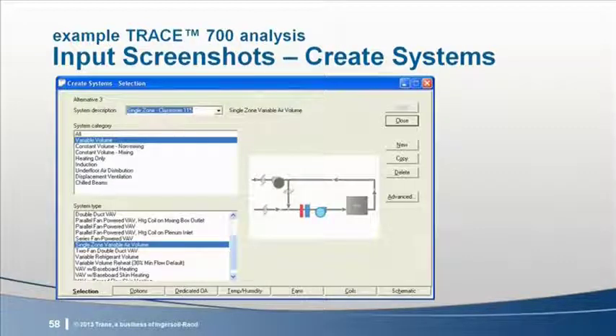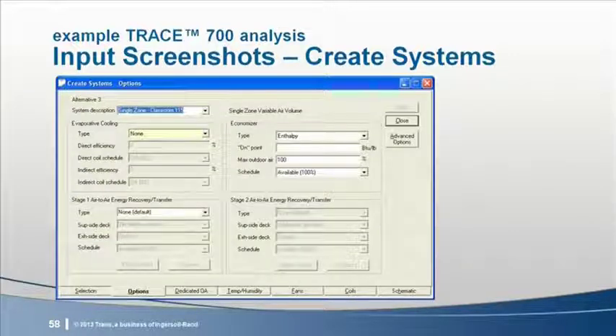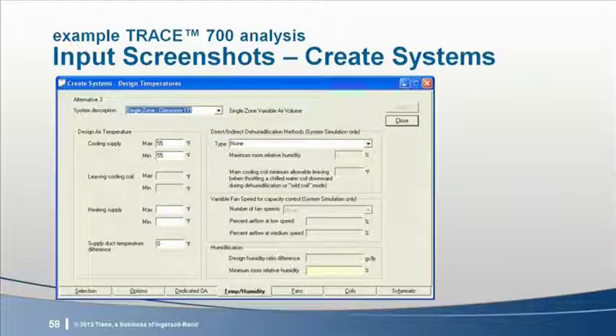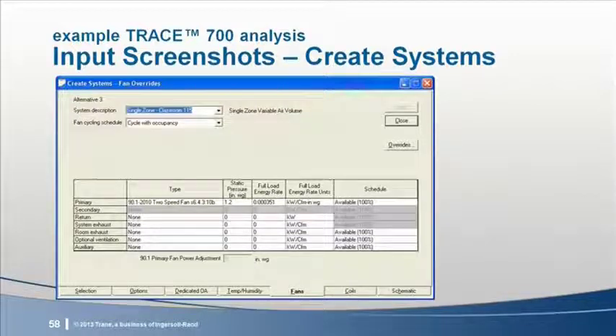Simulating SingleZone VAV systems within Trace is quite simple. First, select the SingleZone variable air volume system from the system type list in Create Systems. Next, you can configure economizer or heat recovery components on the options screen. Skipping forward to the temperature and humidity screen, you can specify coil discharge air temperatures or supply air temperatures at the diffuser. Heating supply air temperatures can also be input. Finally, on the fan screen, you can specify your system fans, including supply and exhaust. You're able to define the full load energy rates and fan efficiency information for each.